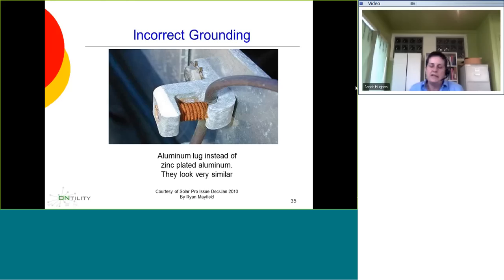What I know about it is that it states that the smallest size wire that you can use solid, that you can use unprotected, is a number 6, and that's what the code reference says. So if we're on a roof, or if we're on a ground mount system and we want to run the bare copper without running it in conduit, we have to use a number 6.